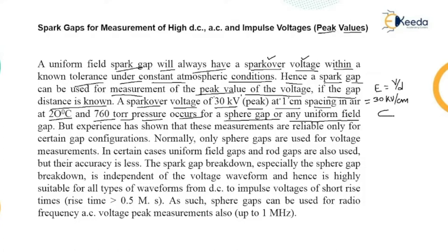This occurs for a sphere gap or any uniform field gap. A uniform field gap consists of two disc electrodes placed and separated by a certain distance — for example 1 centimeter. Application of 30 kilovolts across this 1 centimeter gap produces a spark over voltage. It is called a uniform field gap because the cross-sectional area and volume of both electrodes is the same throughout.